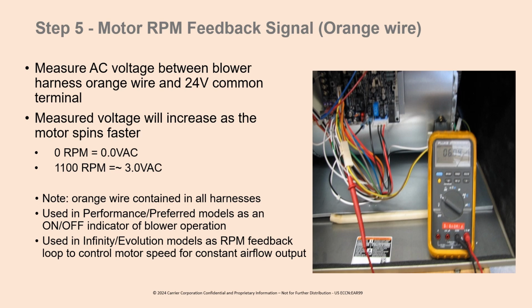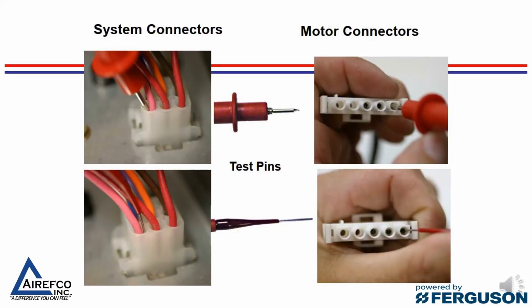This is used in the performance and preferred models as an on-off indicator of blower operation. It's used in the Infinity and Evolution models as an RPM feedback loop to control the motor speed for constant airflow output. As always, when making these checks on the motor plugs, you should use the skinny test probes so you don't damage any of the wires or the plug connections.